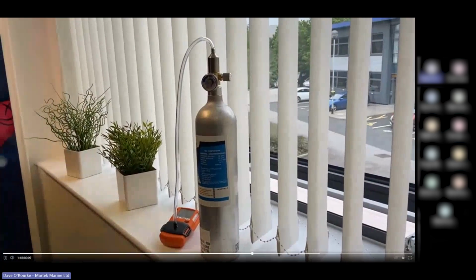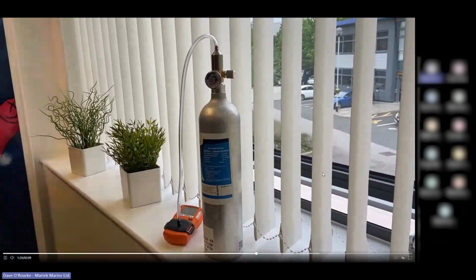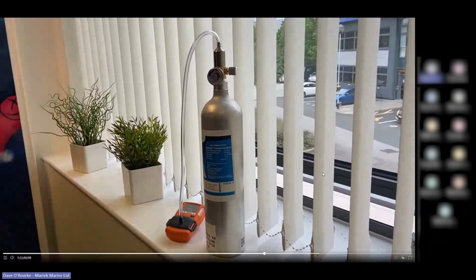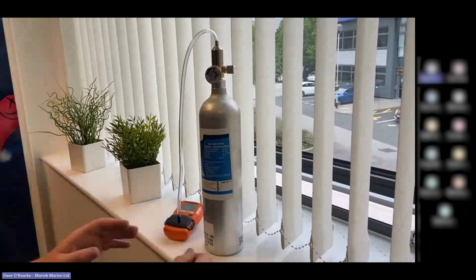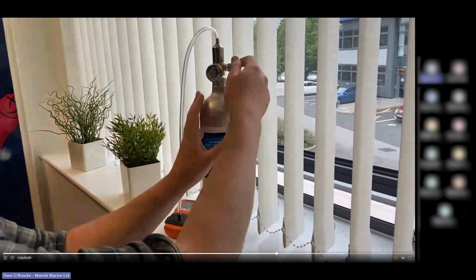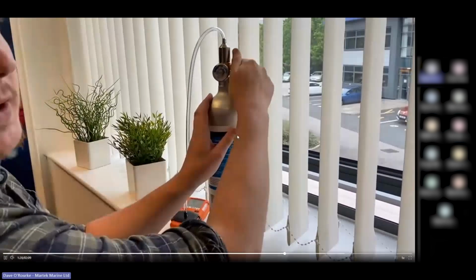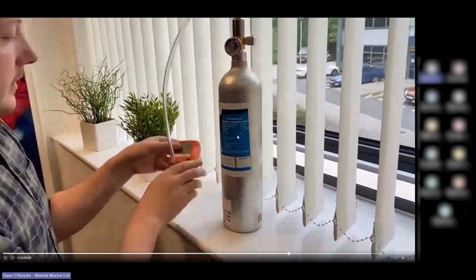Now that these are being tested, we know that it is working. It has gone into an alarm, making sure that it's reading. Once this is done, we can turn it off and remove the calibration cap. Now it will continue to alarm shortly. As you say, it is very loud, but after a moment or two, that will go back to normal. So that's how easy it is to do a bump test.